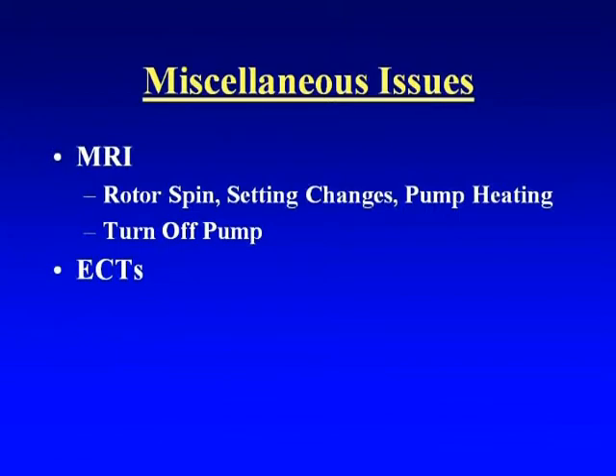In the MRI, the rotor is made of ferrous material, so it aligns in the electromagnetic field. As the motor in the pump tries to turn, if the magnetic field is held in one position, the rotor could be stuck, if you will, or stalled. Part of the programming in the pump allows for detection of a stalled rotor, and it will show that the rotor is stalled. Sometimes just reprogramming the pump can get it going again.